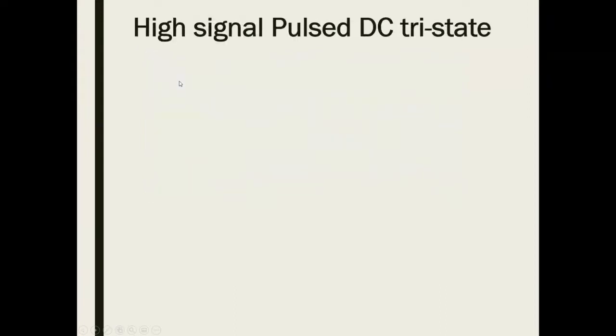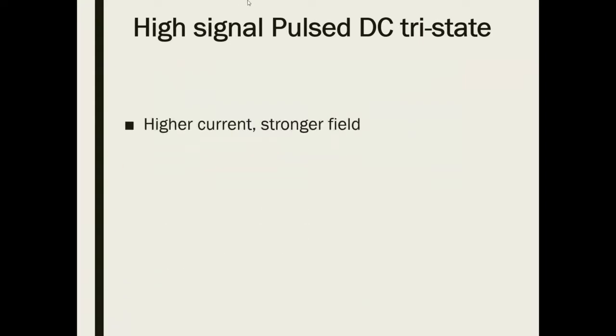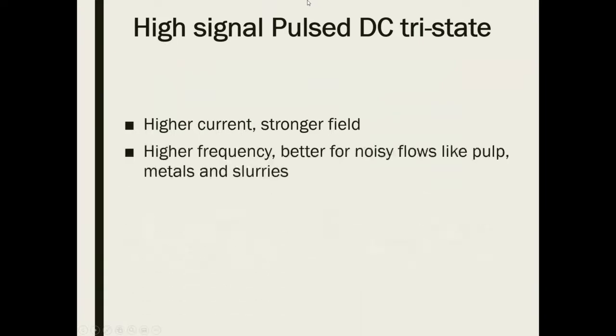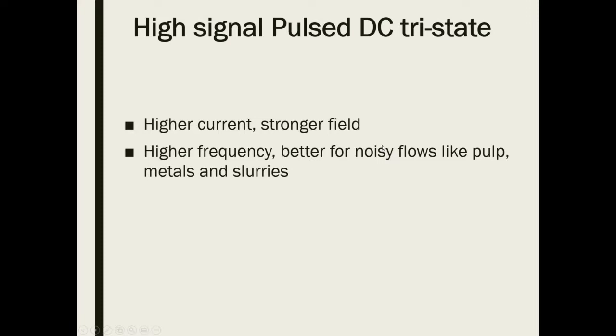The fourth type is high signal pulse DC tri-state, essentially the same as pulse DC tri-state but with a higher current creating a stronger magnetic field, and a higher frequency. This makes it better for noisy flows like pulps, metals, and slurries. We'll talk more about noisy flows in a different lecture in this flow section.